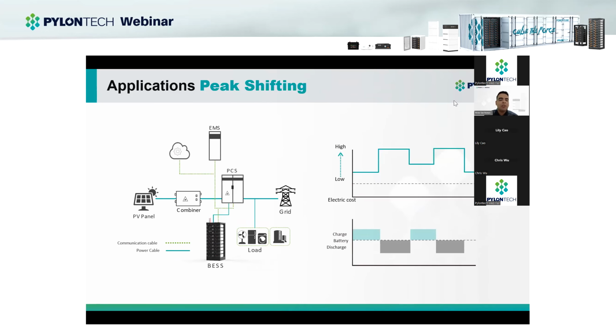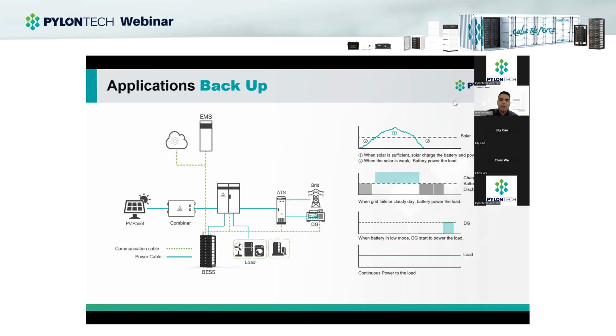Then we have the backup solution, which is a very common one. For this, we need to maintain the loads powered all the time. In this scenario, when we have solar production, solar will go to the loads and also charge the batteries. If solar was weak and we want to configure it that way, batteries can also power the loads.